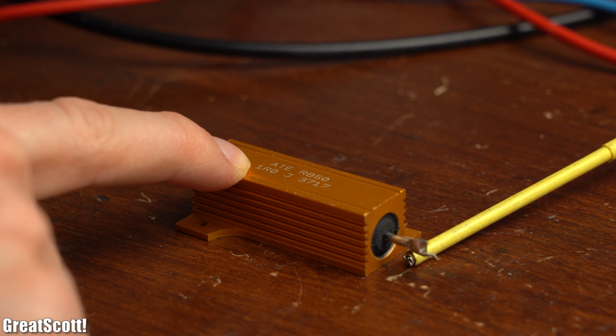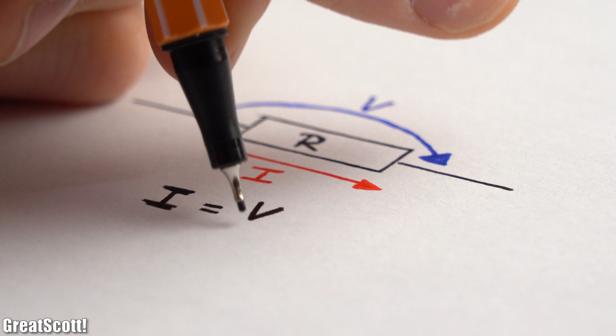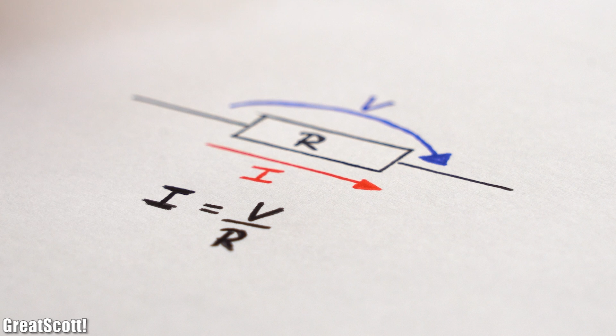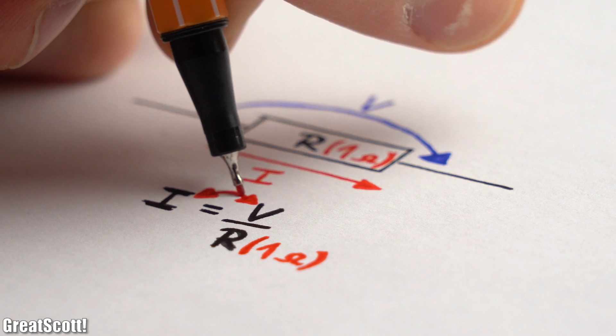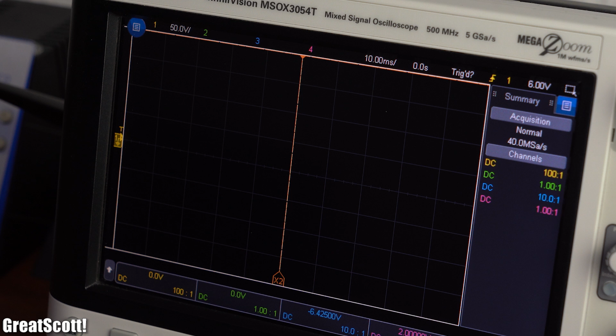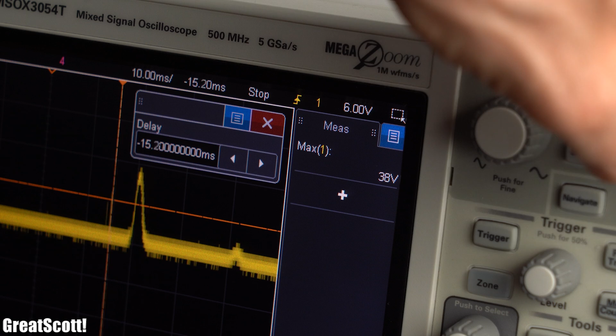Next, to further investigate, I added a 1 ohm current shunt in series with the live wire, whose voltage I monitored with my oscilloscope. As you might know, the current flowing through such a resistor is the voltage across it divided by the resistance, and since the resistance is 1 ohm, the monitored voltage will equal the flowing current. After once again powering up the system, my oscilloscope found the culprit by recording a fast voltage peak with a maximum value of 38 volts, so 38 amps.